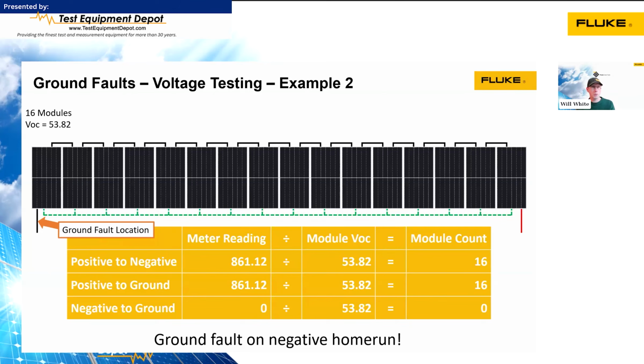This is a relatively common ground fault location, in one of the home runs. It's also fairly easy to miss because you're used to seeing 861 and 0. So you may do that positive to ground measurement and see 861 and be like, yeah, that's fine, and then move on. So when you're doing those measurements, make sure to pay really close attention to what measurement you're getting and whether that's the actual expected measurement.